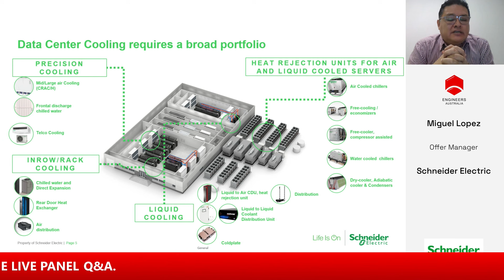Rear door heat exchangers are a good design to have as part of your mix of equipment to cater for these applications, which we'll discuss in the next few slides. Moving across, we have liquid cooling. This is essentially now hardware that needs to reside in these facilities, such as the cooling distribution unit. It could be liquid-to-liquid cooling distribution, or it could be liquid-to-air. Depending on your server manufacturer's specification or the adoption of the high-performance compute server for your facility, you may have customers requiring their server vendor's liquid-to-air solution. If there's such a requirement, Schneider is now positioned to deliver these liquid-to-air cooling distribution units. But what we're finding in Pacific, Australia, New Zealand, typically, is that most customers are looking for liquid-to-liquid cooling distribution units.